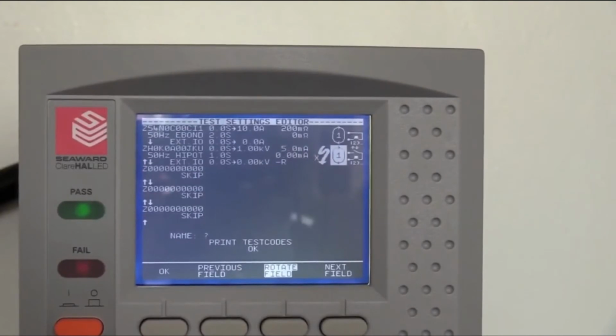Again, we can choose the number of times we want to repeat the test. In this case, because we're testing an Earth product, we're going to be testing the Hipot test via the live and neutral conductors strapped together versus the Earth return cable. So because we've already tested that the Earth path is in existence, it's feasible that any current flow that strays away from the live and neutral conductors should in theory hit any of the external metalwork and therefore would flow back down through the product via the Earth cable of the device under test. So therefore we're only going to need to perform the test once, and we're going to start the test again in this instance just by pressing the green button.